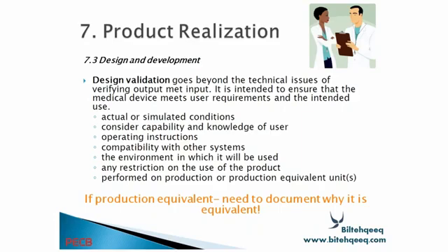Actual or simulated conditions consider capability and knowledge of user, operating instructions, compatibility with other systems, the environment in which it will be used, and restrictions on the use of the product, performed on the production or production equivalent units. If production equivalent, you need to document why it is equivalent. So you have to document each and everything.